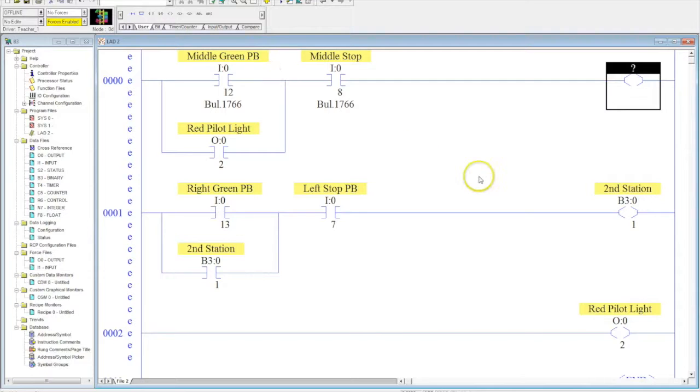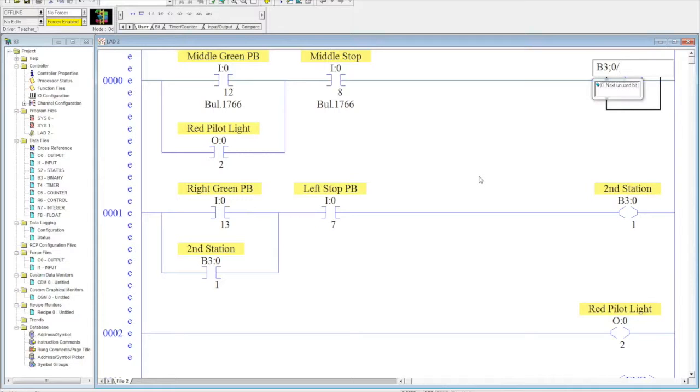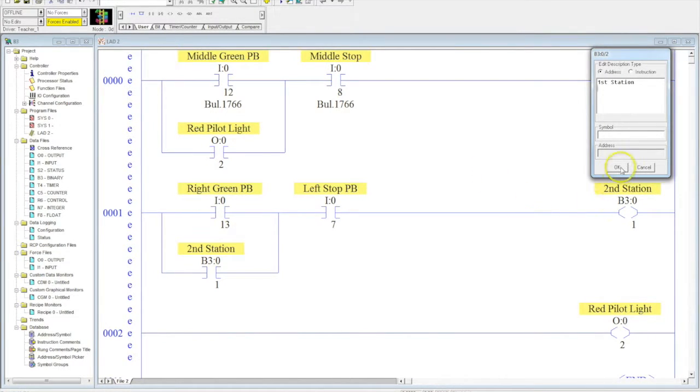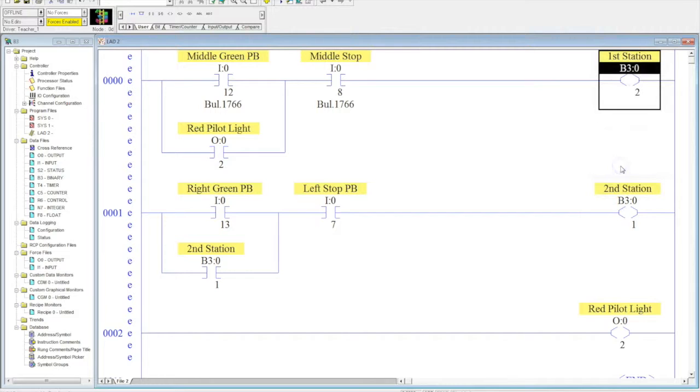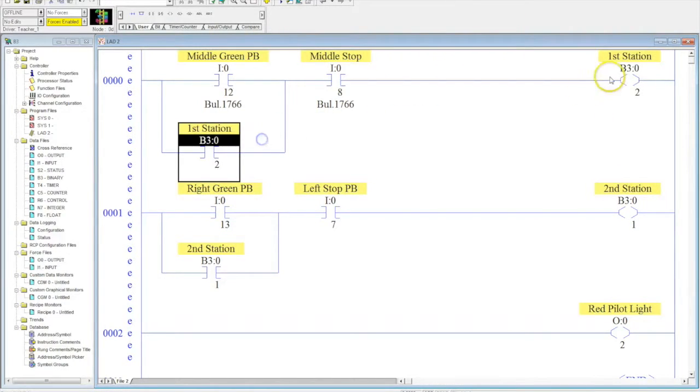Then I need to add another rung down here. Drag my output down to here. Now I need to add another B3 in here. And I seem to be taking a couple of goofy steps here, and you'll see why I'm doing it this way here in a second. So I'll start a new B3. I'll identify it as 2. And this will be first station. And I could put internal relay, I could put bit there, totally depends. Then I need to change this memory. Always do this. If you ever change this output, you always have to change that memory associated with it. It is such a common mistake. An easy one to make. You can't blame anybody for making that mistake.